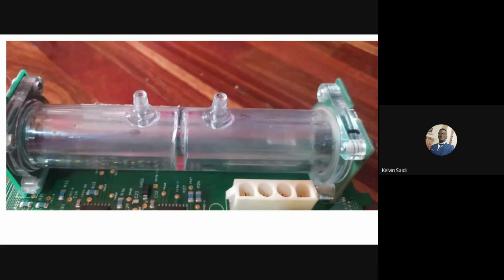So in order to sense oxygen, a sonic wave is generated by one of the transducers and transmitted to the other transducer, which transforms this sonic wave into a voltage corresponding to the magnitude of the wave, to the speed of the wave. The speed of sound varies in these two types of gases. In oxygen, the speed of sound is 332 meters per second, and in nitrogen, it's 354 meters per second. The time taken for the sonic wave to reach the other transducer is used to determine the oxygen concentration. The advantage of ultrasonic sensors is that they are more reliable than the electrochemical sensors.